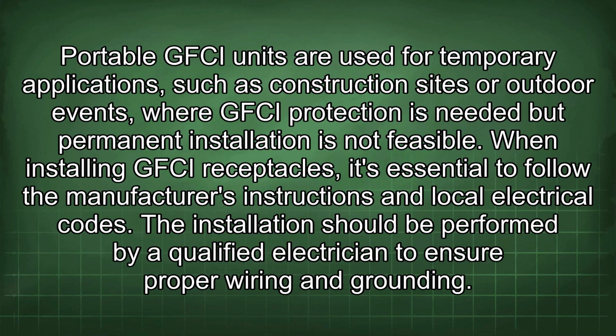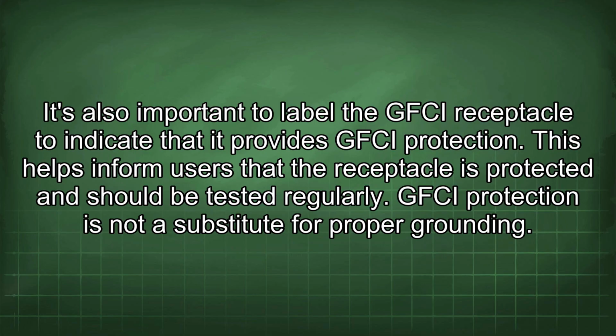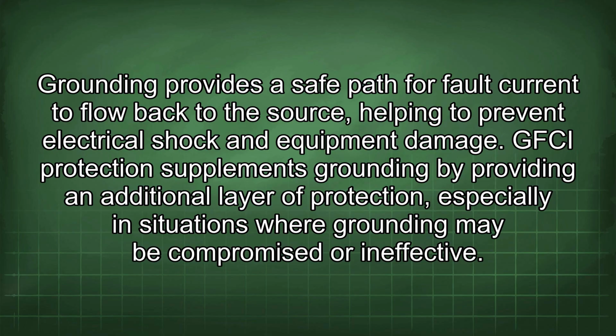When installing GFCI receptacles, it's essential to follow the manufacturer's instructions and local electrical codes. The installation should be performed by a qualified electrician to ensure proper wiring and grounding. It's also important to label the GFCI receptacle to indicate that it provides GFCI protection. This helps inform users that the receptacle is protected and should be tested regularly. GFCI protection is not a substitute for proper grounding. Grounding provides a safe path for fault current to flow back to the source, helping to prevent electrical shock and equipment damage.